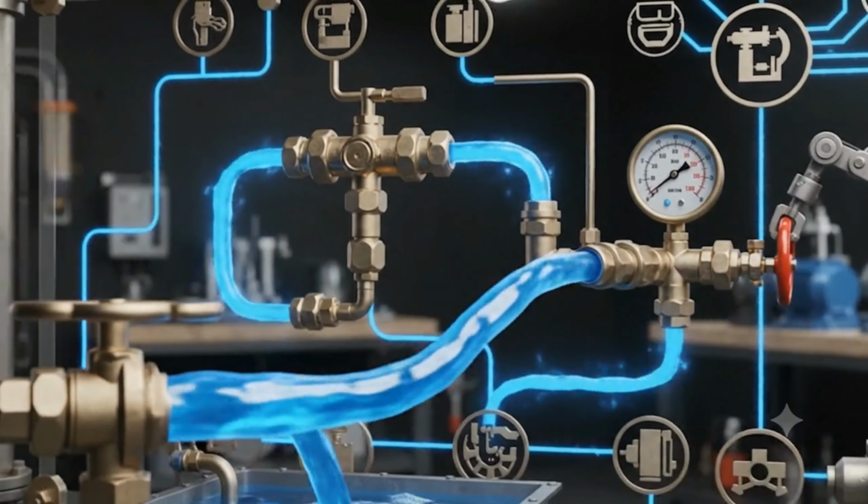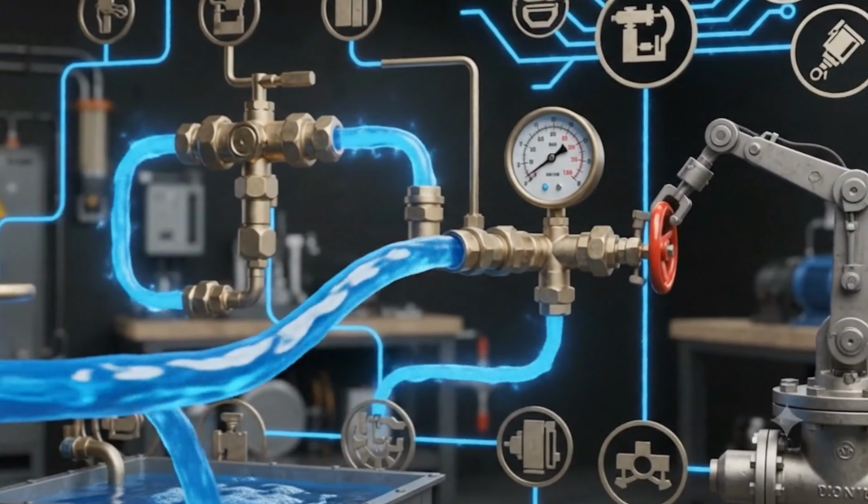The core of any fault comes down to a complete breakdown in flow and pressure. Behind every hydraulic failure, there are only 3 main culprits. Number 1, source failures. The pump is failing to deliver the correct flow. Number 2, leakage. An internal leak breaks the closed circuit, completely destroying your pressure and bleeding away your flow. And number 3, obstructions and switching failures. Your directional control valves are failing to shift into the correct operating positions.